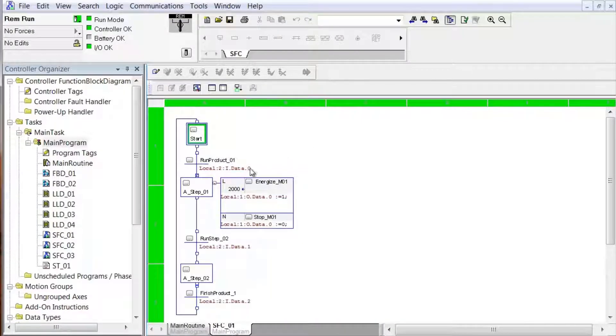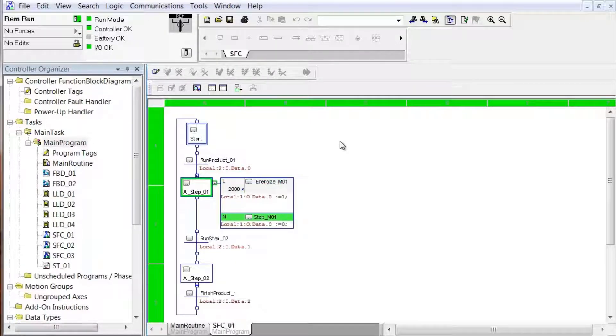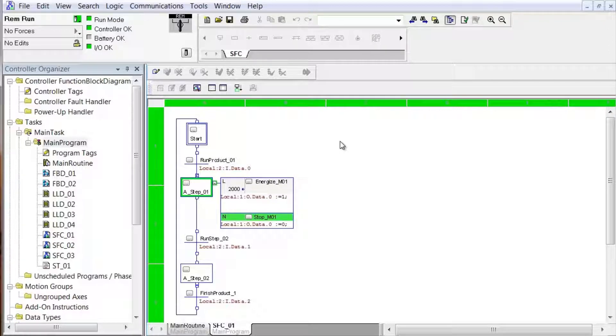Watch very closely. I'm going to press the push button connected to the input module associated with slot 2, input data bit 0. That toggles it in. The light went on for two seconds and then went off. Notice that the time limited action was green for two seconds and then deactivated. The step is still active and the non-stored action is still active. This is just one way to turn on something for a length of time and then turn it back off using actions in the sequential function chart steps.